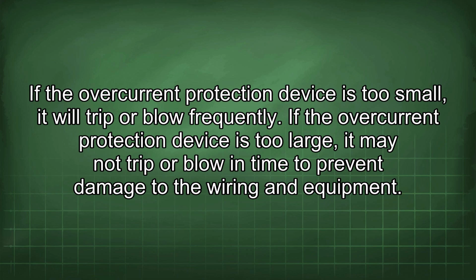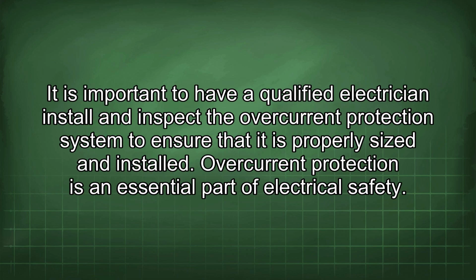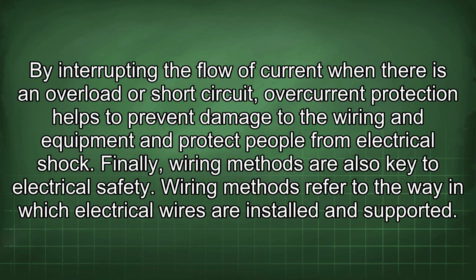If the overcurrent protection device is too small, it will trip or blow frequently. If the overcurrent protection device is too large, it may not trip or blow in time to prevent damage to the wiring and equipment. It is important to have a qualified electrician install and inspect the overcurrent protection system to ensure that it is properly sized and installed. Overcurrent protection is an essential part of electrical safety. By interrupting the flow of current when there is an overload or short circuit, overcurrent protection helps to prevent damage to the wiring and equipment and protect people from electrical shock.